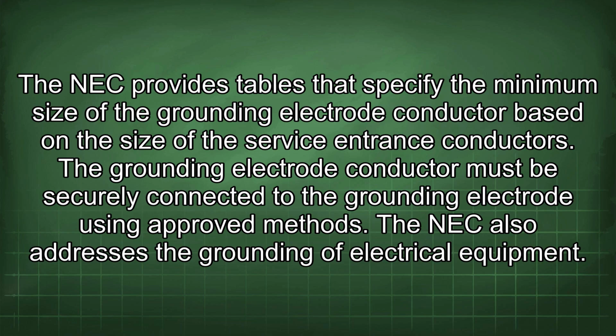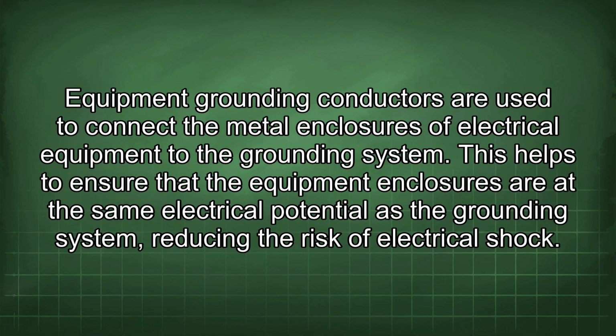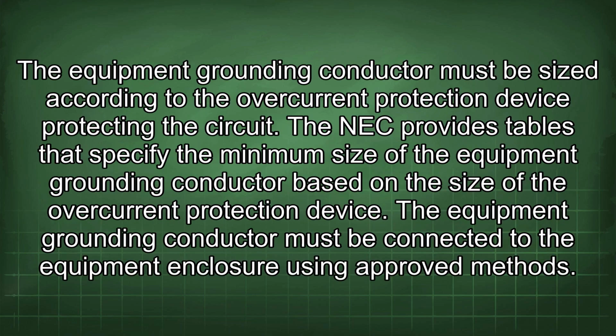The NEC also addresses the grounding of electrical equipment. Equipment grounding conductors are used to connect the metal enclosures of electrical equipment to the grounding system. This helps to ensure that the equipment enclosures are at the same electrical potential as the grounding system, reducing the risk of electrical shock. The equipment grounding conductor must be sized according to the overcurrent protection device protecting the circuit. The NEC provides tables that specify the minimum size of the equipment grounding conductor based on the size of the overcurrent protection device. The equipment grounding conductor must be connected to the equipment enclosure using approved methods.